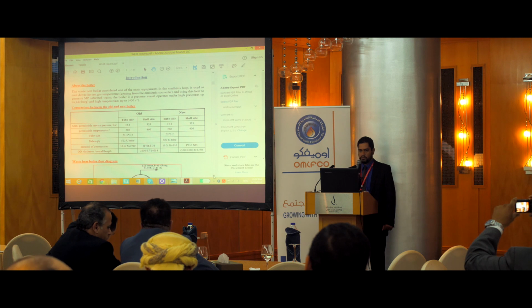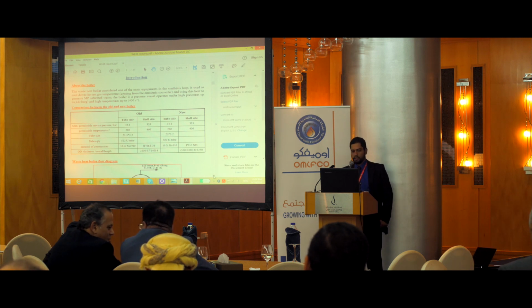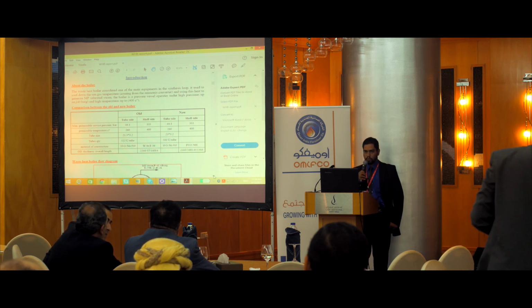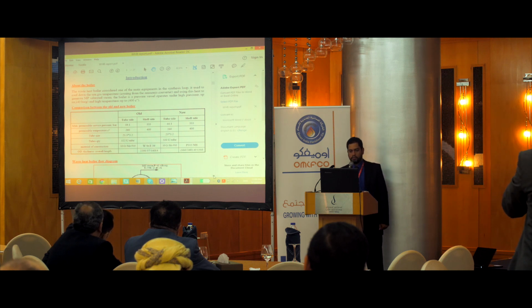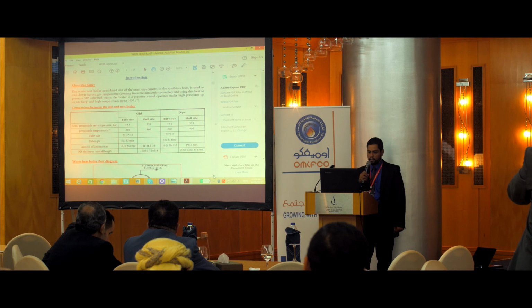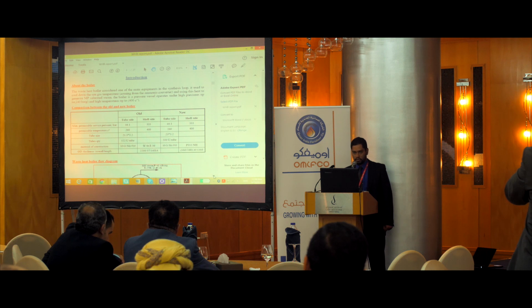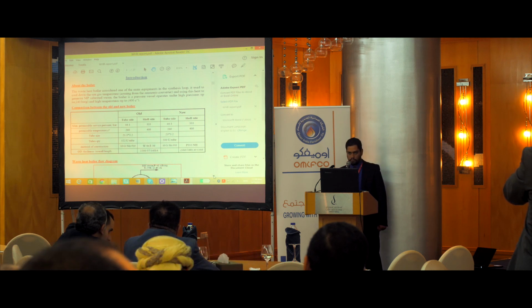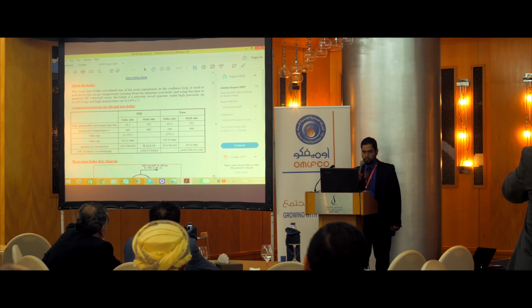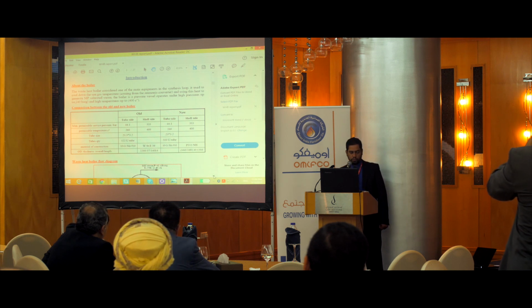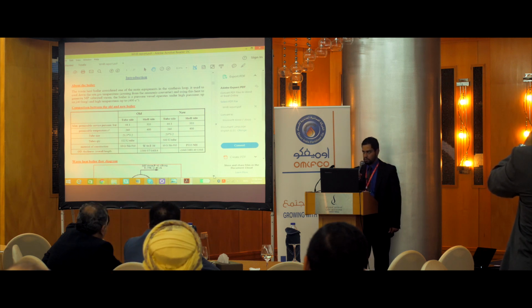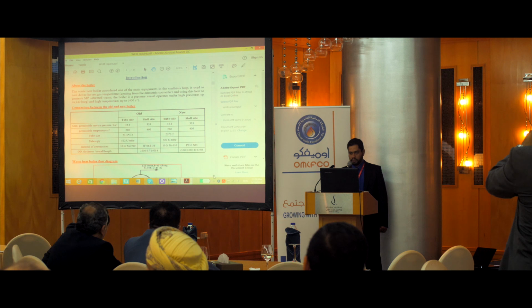We have experienced a lot of leakage in the waste heat boiler and the auxiliary boiler, the main boiler of the plant, which is the source of steam for the factory. In 2011, we experienced low pH in the boiler feed water. It was about 4.5 pH. It was human error. It was a very bad experience.